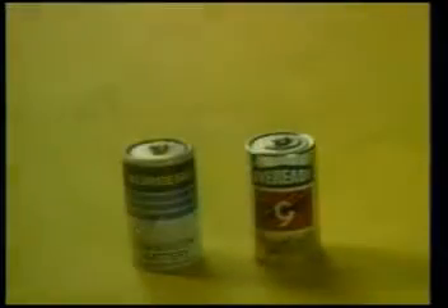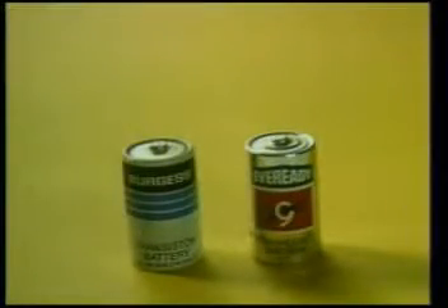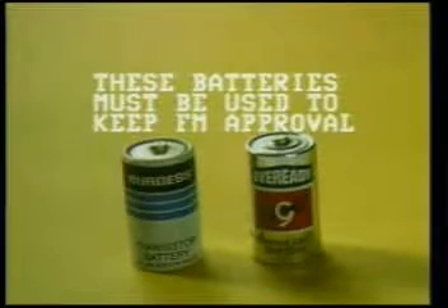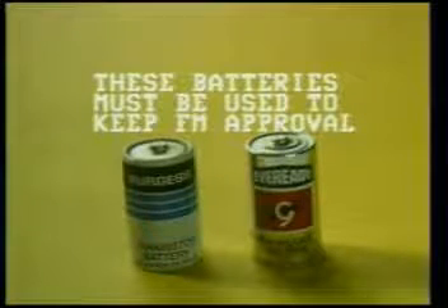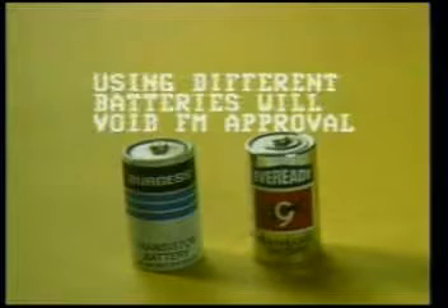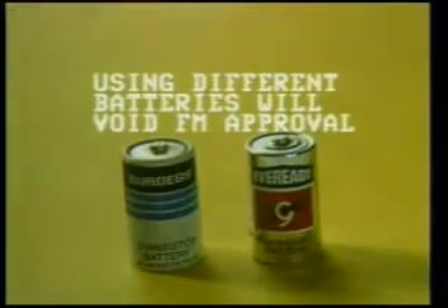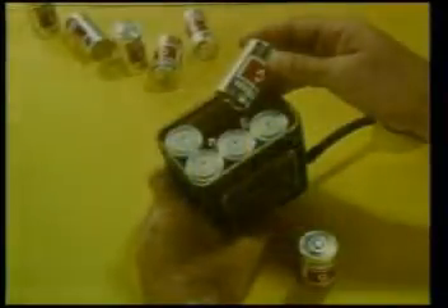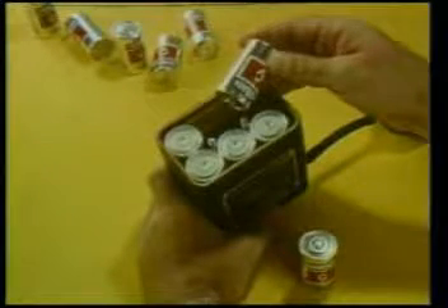The explosimeter indicator uses six D-size flashlight batteries. They should be replaced with Burgess or Ever-Ready batteries only, in order to keep the factory mutual approval for use in hazardous atmospheres. Although other batteries will work, the approval is void, because only these two brands have been tested for use with the instrument. Remove the old batteries and replace them with six new cells with the positive or button side down.